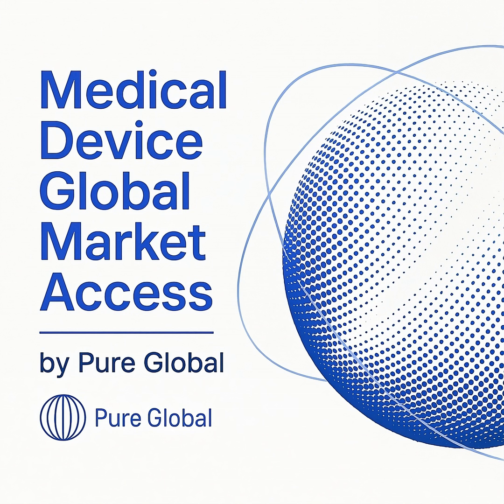They are required to handle medical device reporting, or MDR, submitting reports to the FDA if a device is associated with a serious injury or death. They also manage reports of corrections and removals, and must maintain detailed records of imported devices.